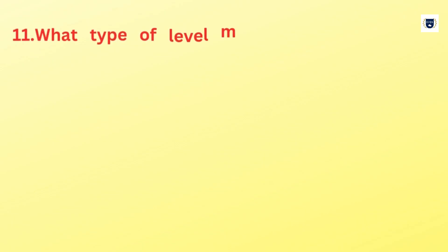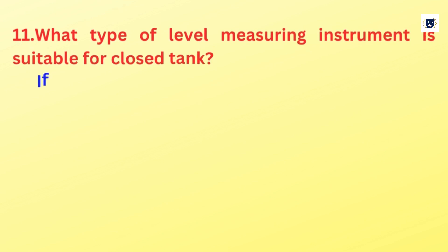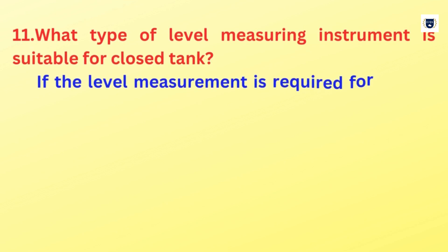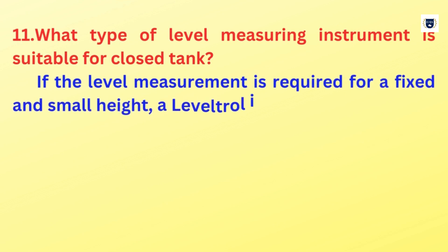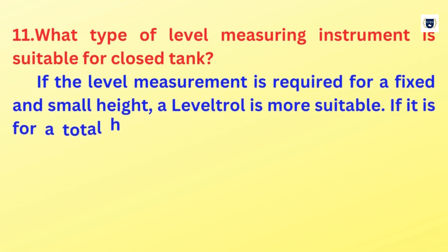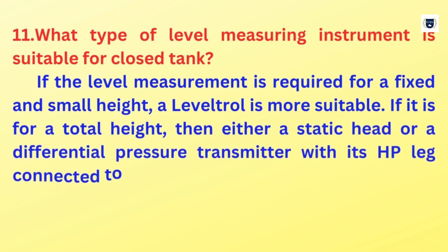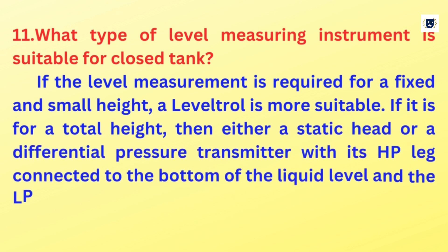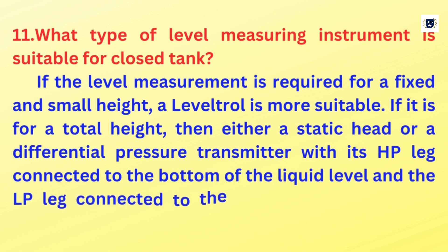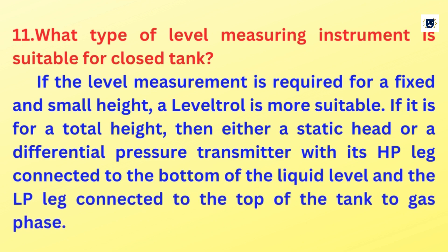What type of level measuring instrument is suitable for a closed tank? If the level measurement is required for a fixed and small height, a Leveltrol is more suitable. If it is for a total height, then either a static head or a differential pressure transmitter with its HP leg connected to the bottom of the liquid level and the LP leg connected to the top of the tank to the gas phase.